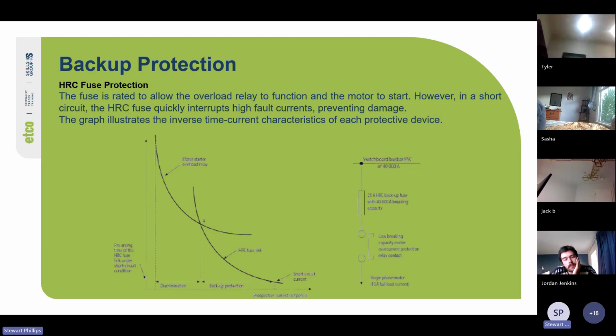The graph below illustrates the inverse time current characteristics of each protective device. So you've got your motor starter overload relay, and then you've got your HRC fuse link. When we say HRC fuse link, normally for a motor, if one HRC blows, it disconnects the other two as well to ensure that all three phases are disconnected at once. And sometimes that facility will also disconnect the neutral.